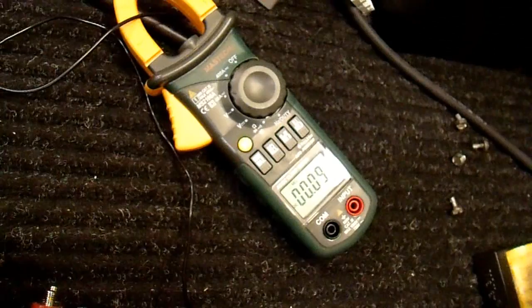Right now it's at 0 amps, both switches are on. As soon as I make contact here, the inverters will try to start up. Let's see what the input current is... and you can see it's very, very low, 0.2 amps or so. Each of these inverters separately probably draws about 0.1 amps from the battery under no load, so they're operating perfectly normally.